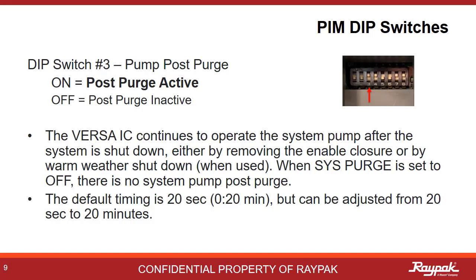PIM dip switch number three controls the post purge option. Post purge allows the pumps and cold water protection system, if equipped, to run for a bit after the burner shuts off. This extra 20 seconds of pump run time gets the residual heat out of the combustion area so you do not trip on a high limit accidentally. The default time is just 20 seconds, but it can be adjusted from 20 seconds to 20 minutes.